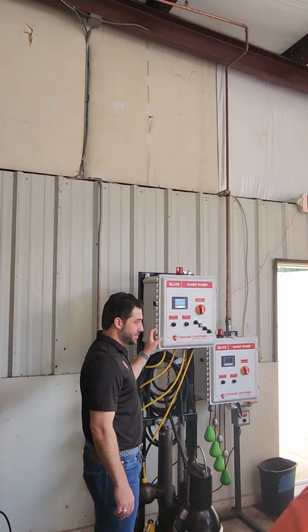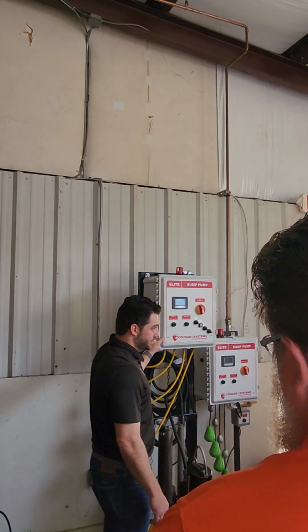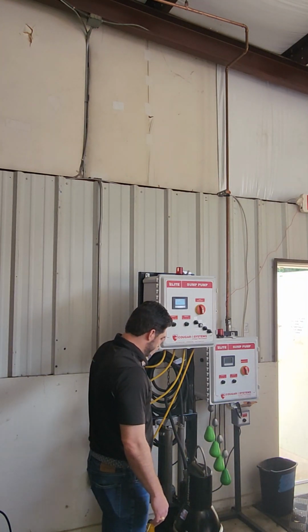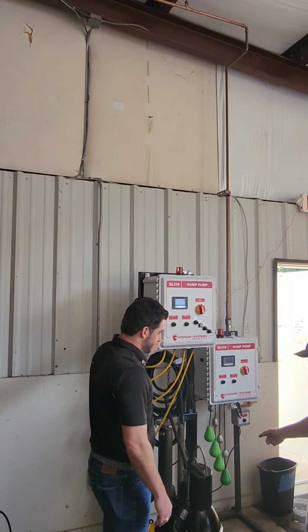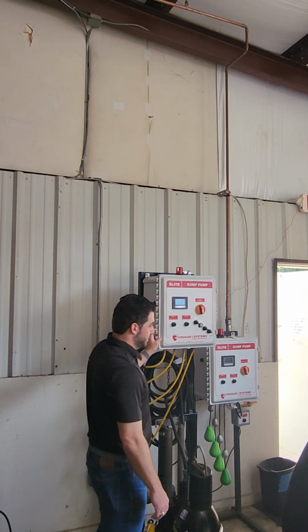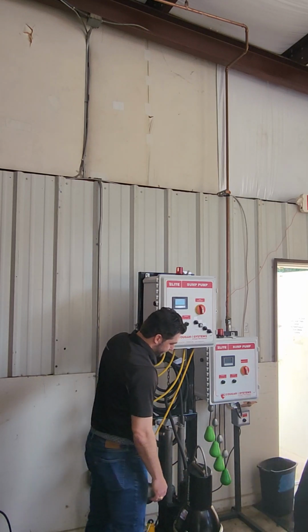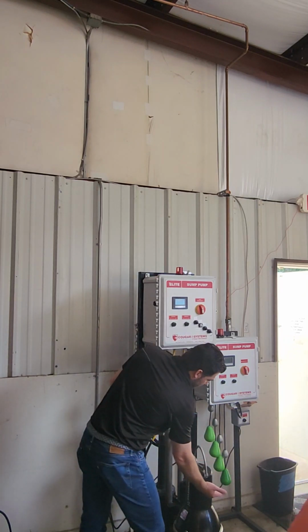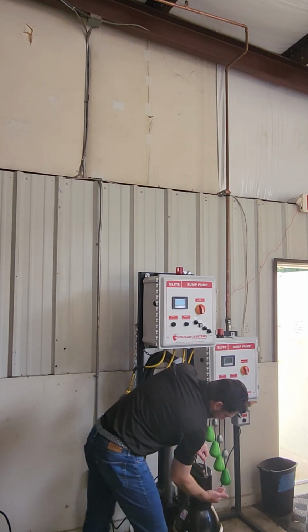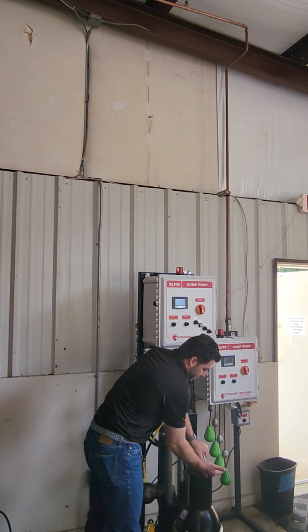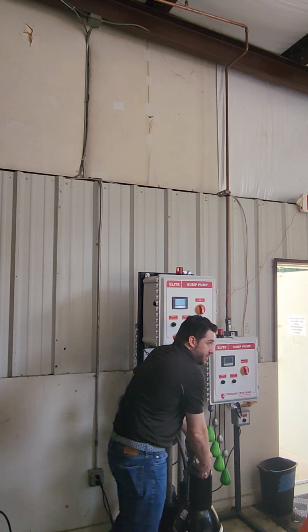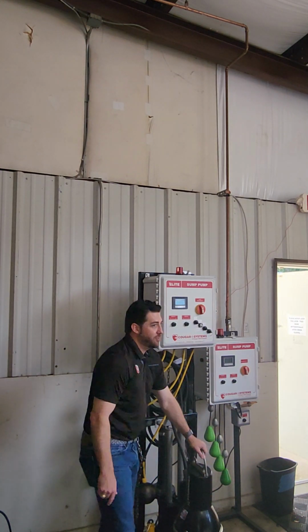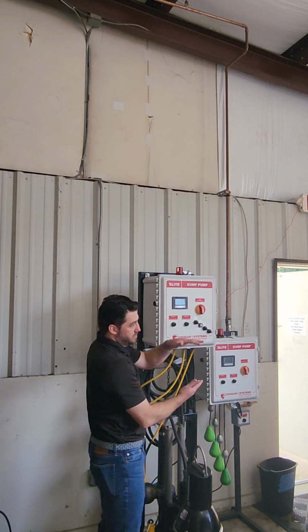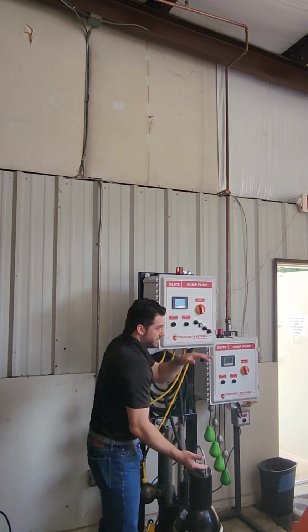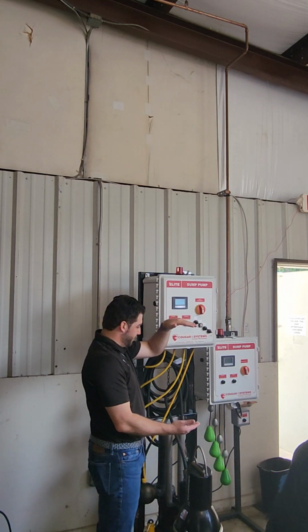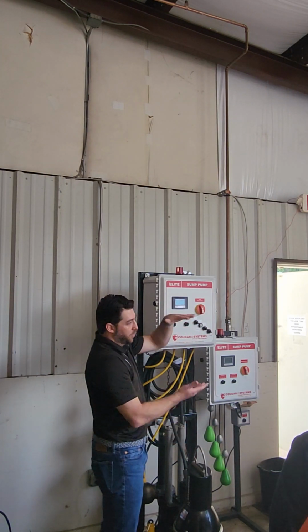So earlier you mentioned the pump being submerged. Yep. What are the two questions? What's the recommended level of your first float? And then what spacing do you recommend between each float? Great question. Depends on your outlet, no? You don't want to let the pump go more than halfway down the motor, so you have enough room and you can leave it always underwater. You can typically go down to about halfway on the motor if you need that extra pump down. But basically, you have from there to your invert, coming in. That's the usable space of the pit.